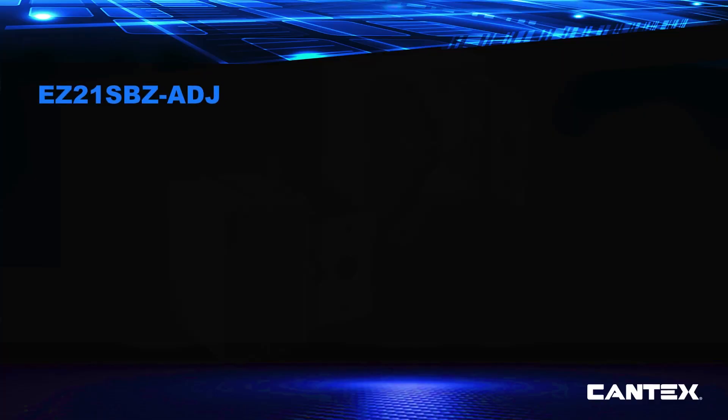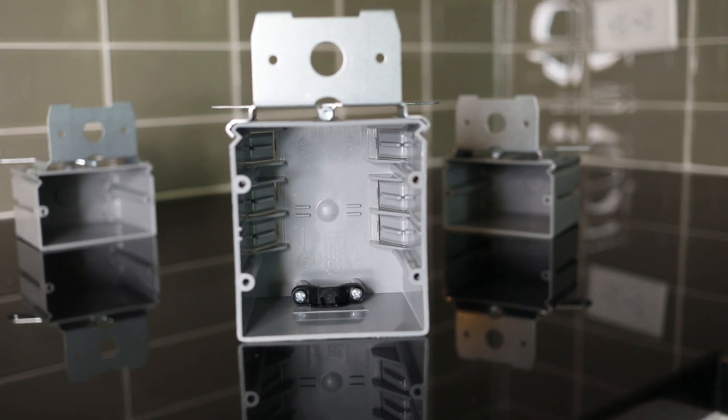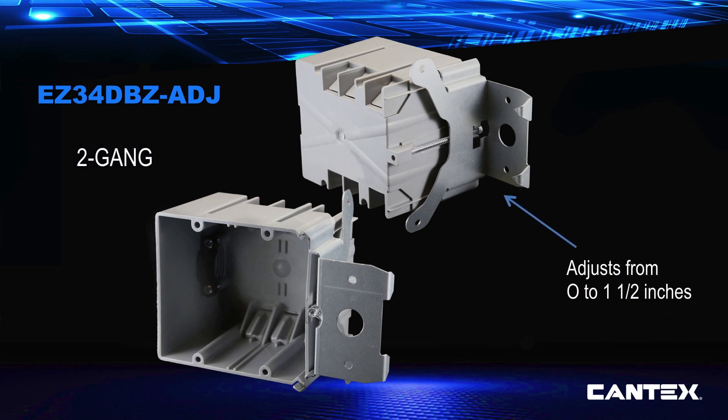The EZ21SBZ-ADJ is the Cantex single gang 21 cubic inch large capacity adjustable PVC switch or outlet box that adjusts from 0 to 1 and 3/4 inches. The EZ34DBZ-ADJ EasyBox is Cantex's two gang 34 cubic inch large capacity adjustable PVC switch or outlet box that adjusts from 0 to 1 and 1/2 inches.